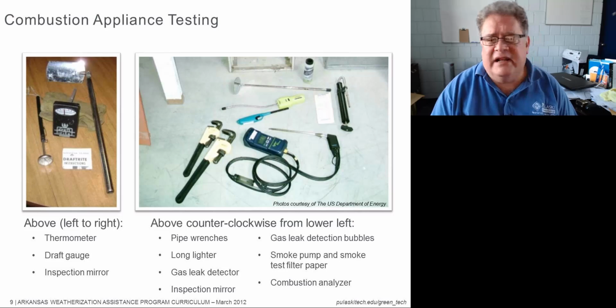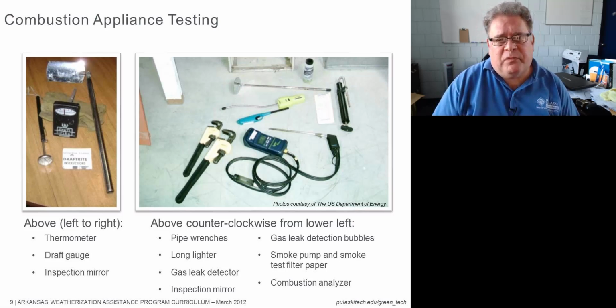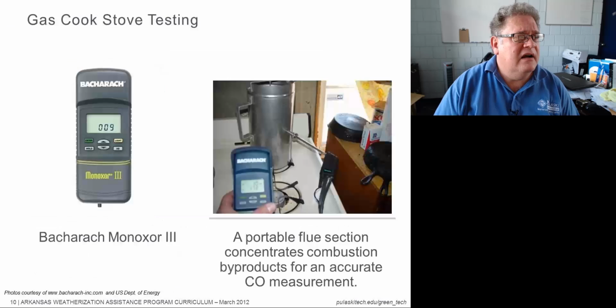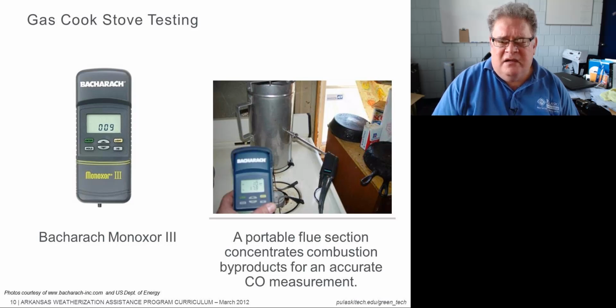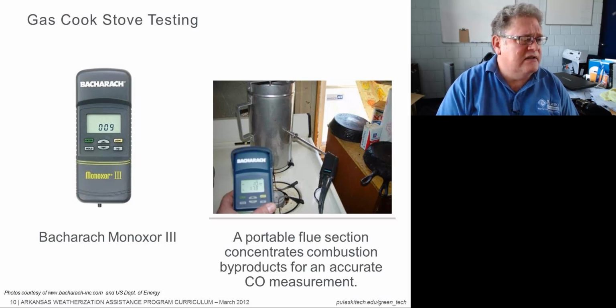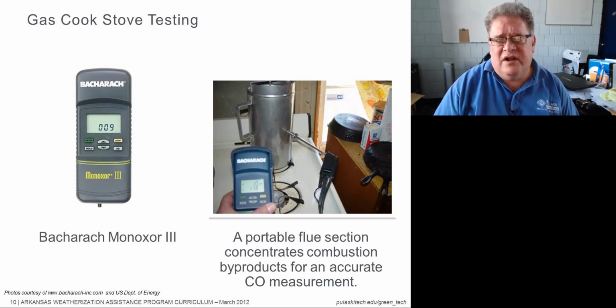You want to have a good combustion analyzer. When we're testing cook stoves, a single-purpose instrument like a Monoxor is pretty good, but it's only good at measuring CO in ambient air. And what I mean by ambient air is the air around us, or just a particular sample. When you take a piece of flue and concentrate the exhaust gases so they're not mixing too much with the ambient air around it.